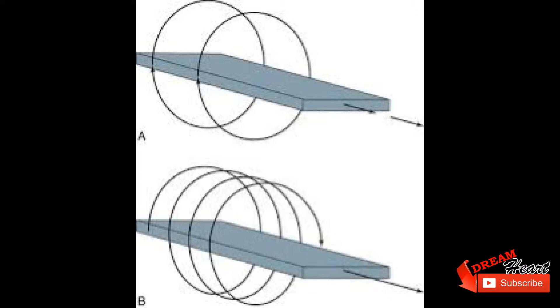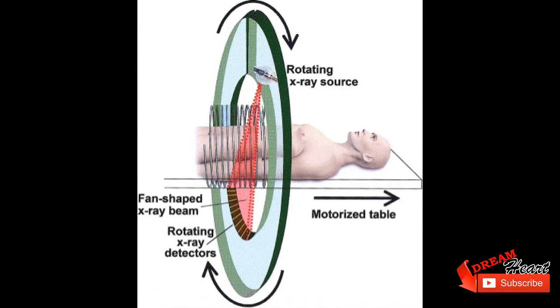In helical CT, the x-ray source is attached to a freely rotating gantry. During a scan, the table moves the patient smoothly through the scanner. The name derives from the helical path traced out by the x-ray beam.